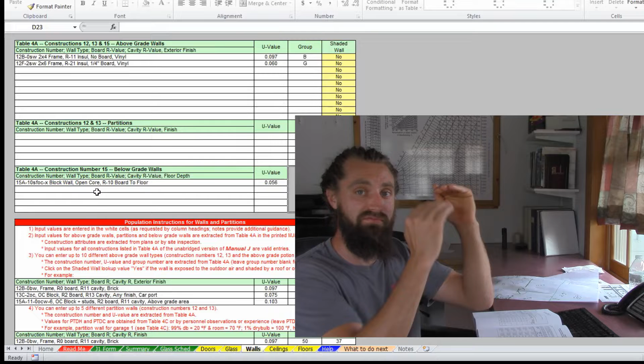That's what we're specifying right here. I've got R10 blue board insulation that goes from the sill all the way down to the footer, or to the finished floor of the basement. So this is my U value associated with that, a 0.056. If you had any other type of construction, you would associate that with whatever you found in the book. So that's it for our walls.